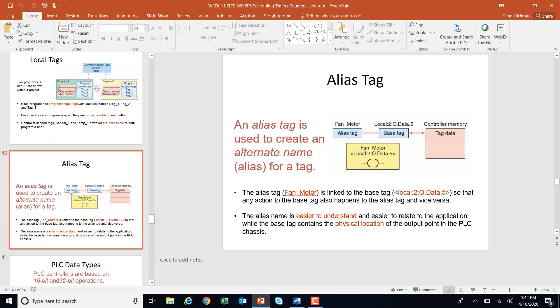An alias tag is the name we use for the data. The base tag — for Allen-Bradley this might be something like Local:2:O.Data.5 for slot 2, output, bit 5 — that's the memory address. It's hard to remember that address, so we just call it fan motor. Fan motor is the alias for that data location. When you want to put your tag in, you click, pull down, find fan motor, and it's already addressed because you created that tag ahead of time.